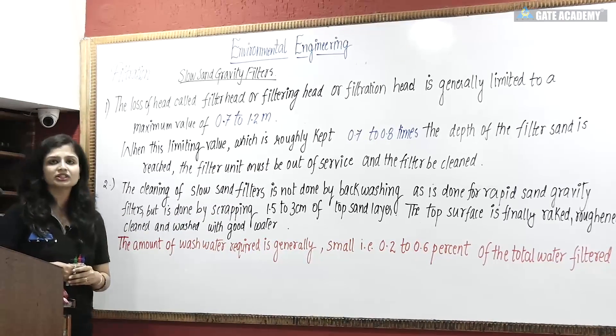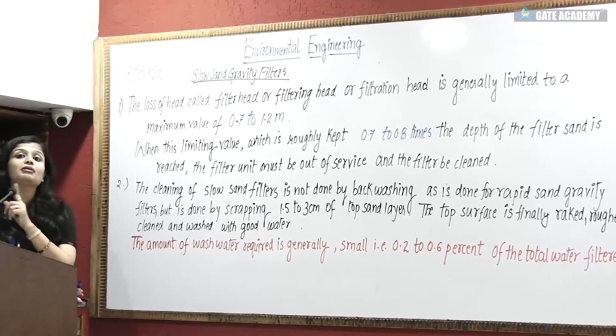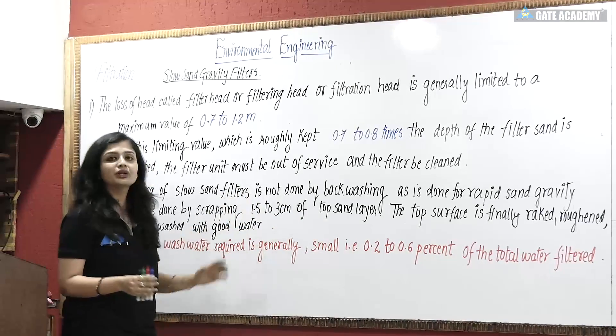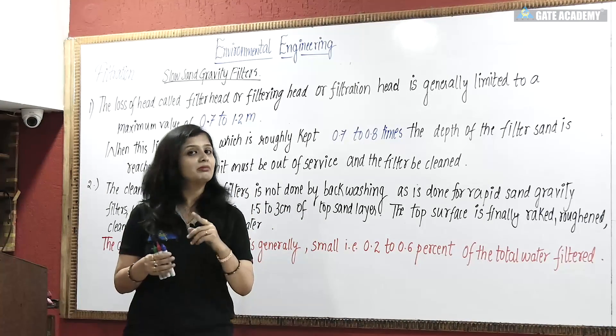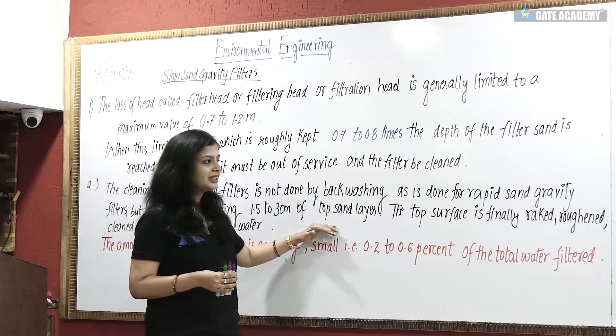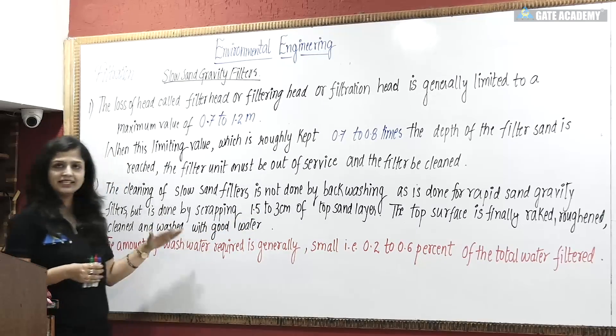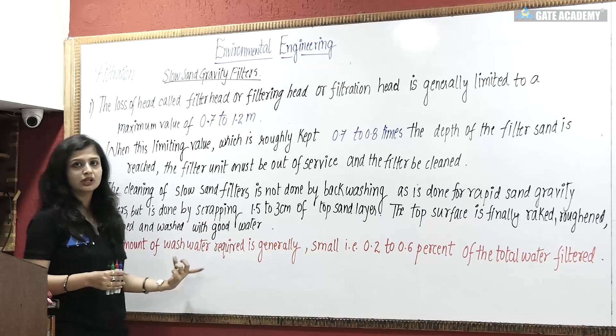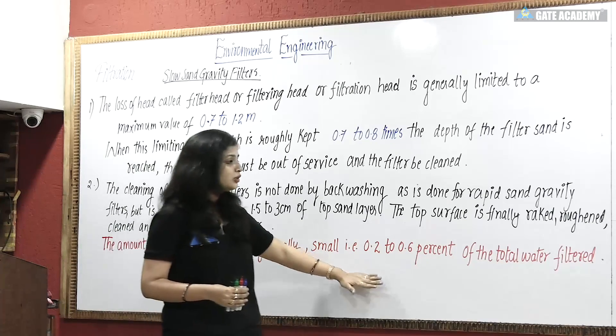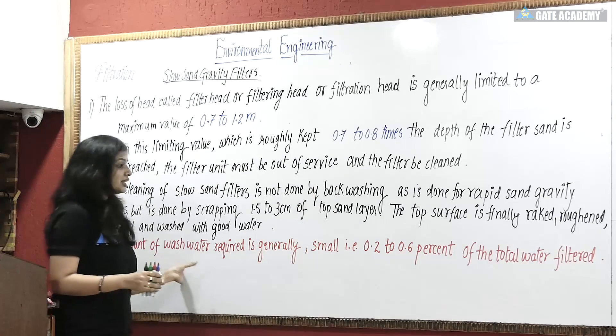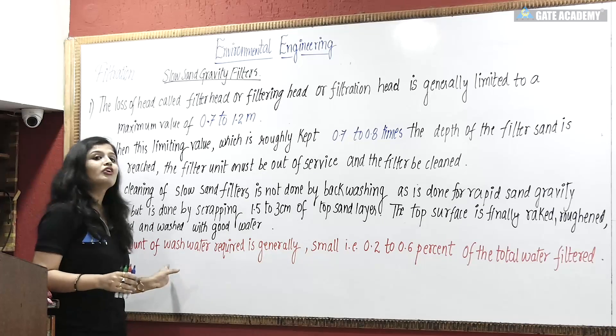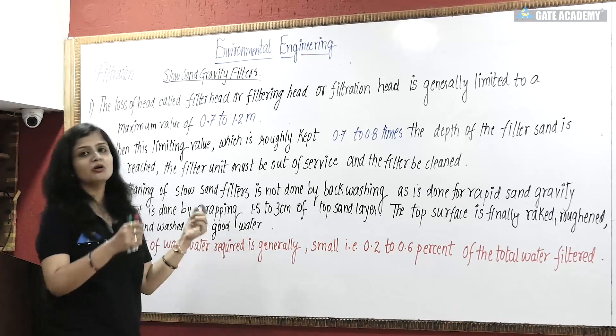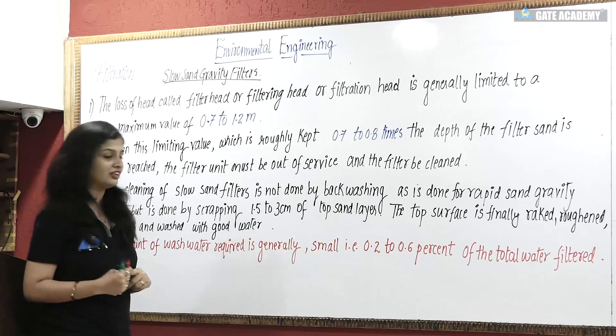The cleaning of the slow sand filter is not done by back washing, as is the case with rapid sand gravity filters. Instead, it is done by scraping the top 1.5 to 3 cm sand layer. We scrape the finer sand particles, rake them, then clean and wash with filtered water. The amount of wash water required is 0.2 to 0.6 percent of the total filtered water — much less than what is required for rapid sand filters.